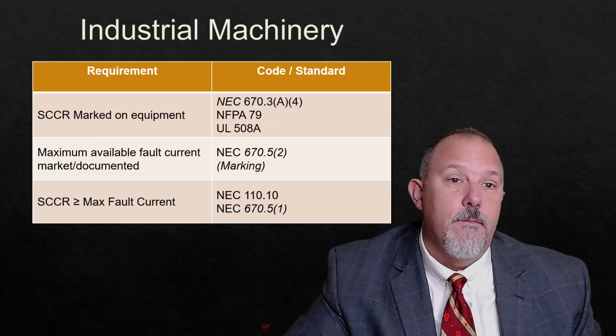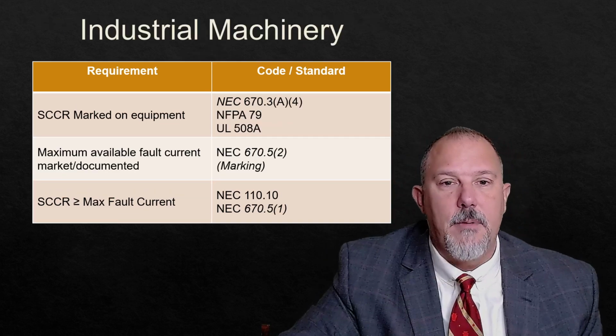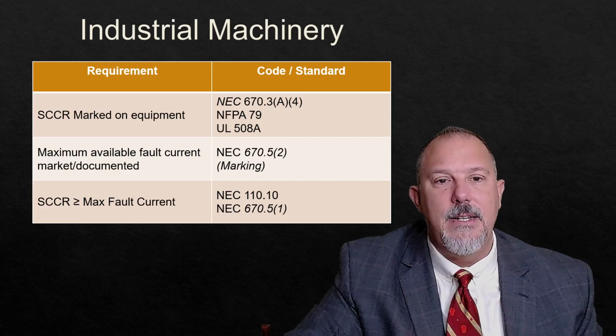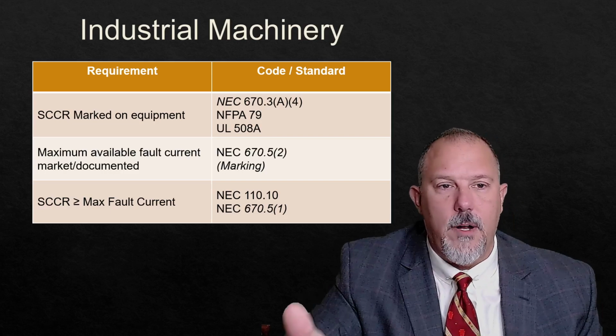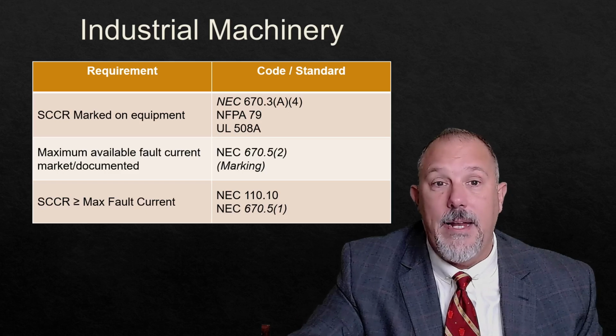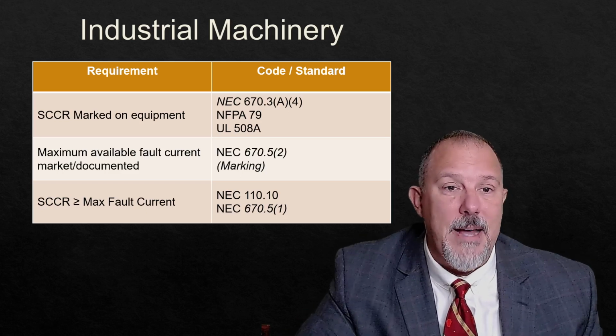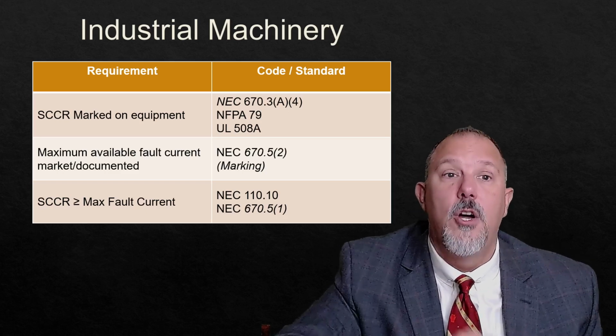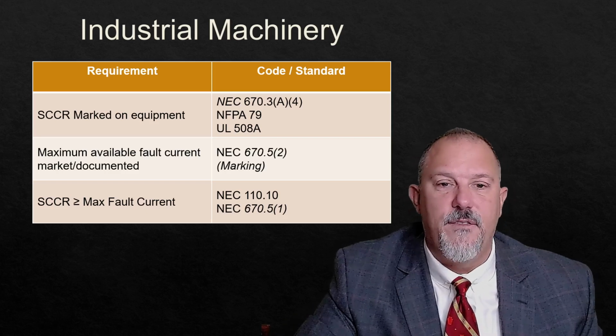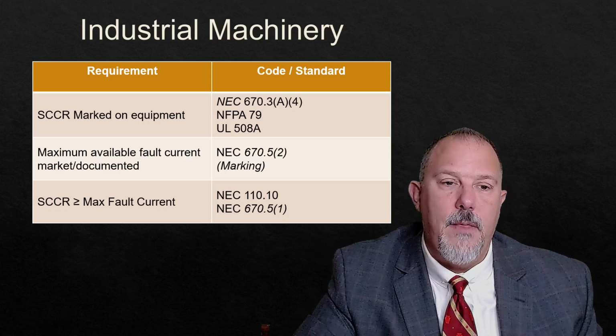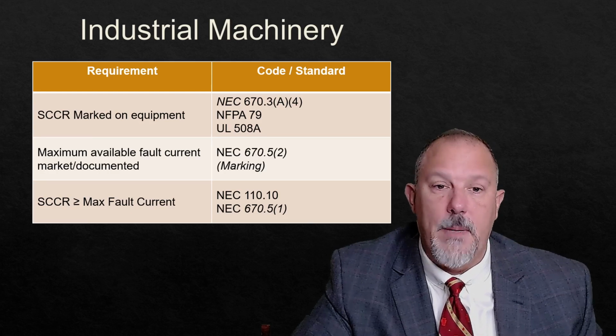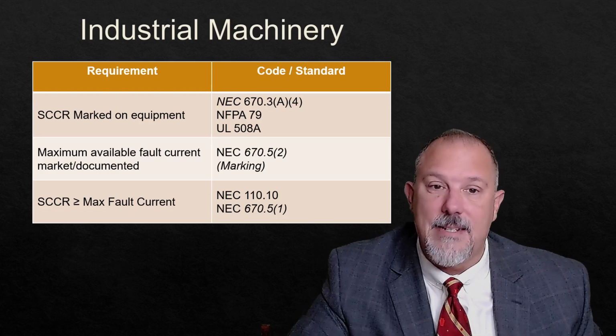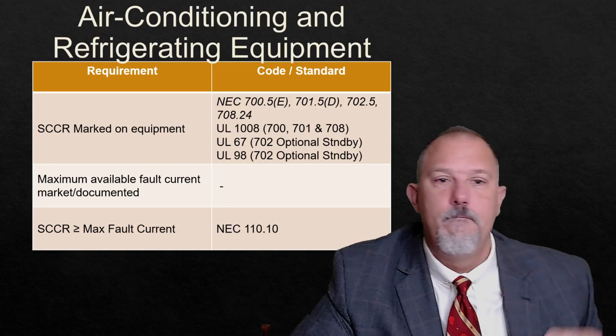Industrial machinery, 670.3A4, NFPA 79. Those are places where you're required to mark the SCCR rating, or if you buy a listed product. Maximum available fault current has to be marked on industrial machinery, 670.5, paren 2. And then you have to compare the two numbers based on 110.10 again, always, and 670.5, paren 1.